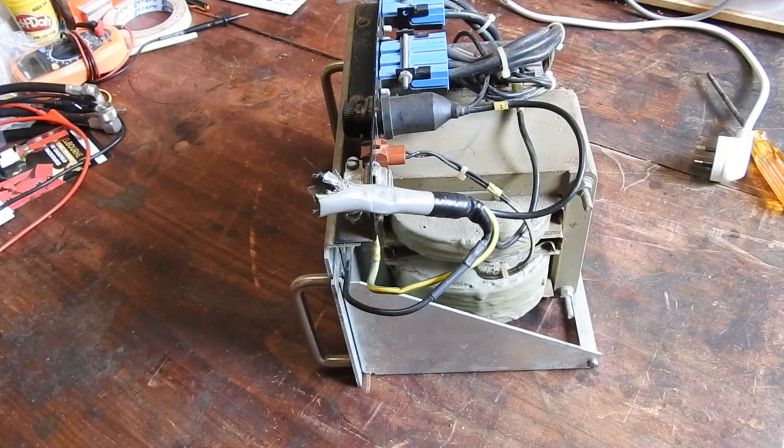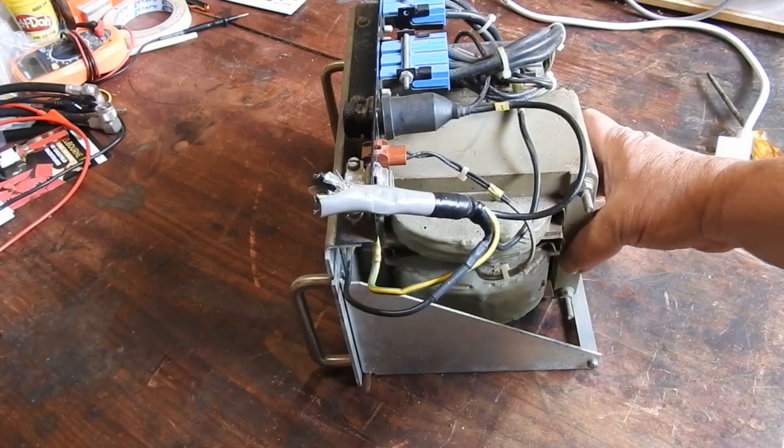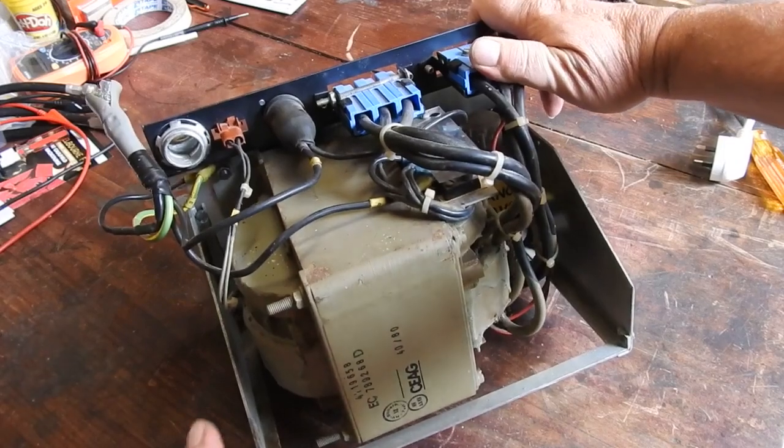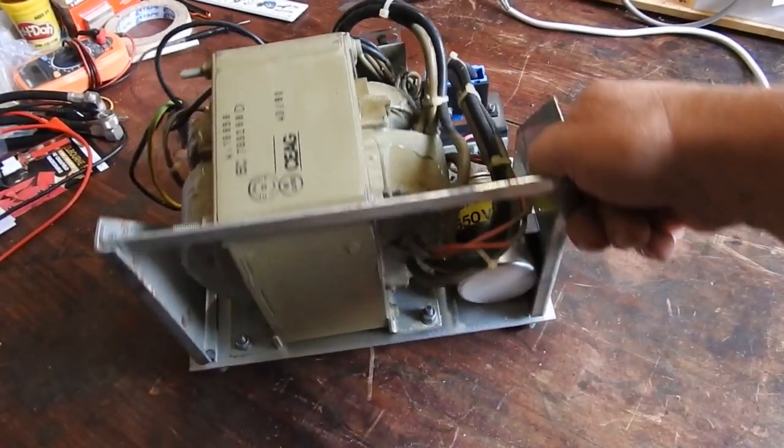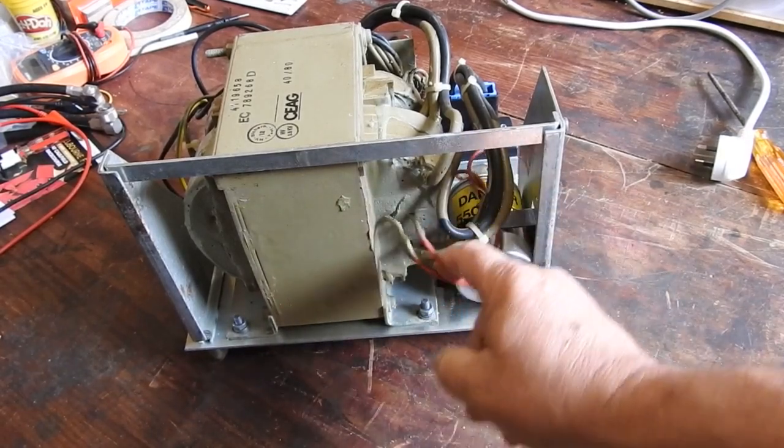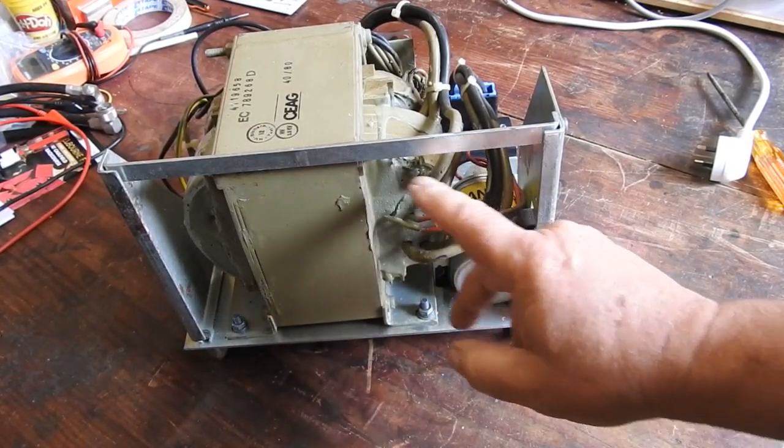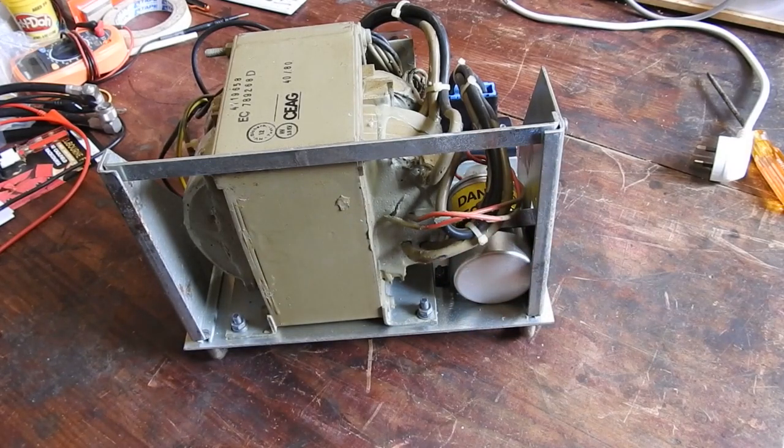Now what makes it different to an ordinary transformer? Well, this capacitor down here. That capacitor has got its own secondary winding that's in parallel with it. And those two, the capacitor and that winding, form a resonant circuit which is tuned to the 50 Hz mains.